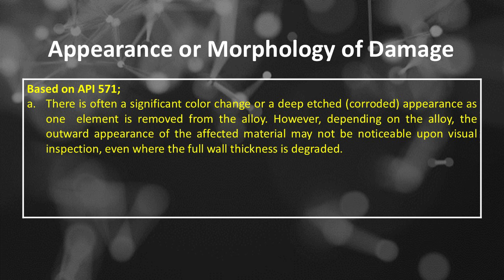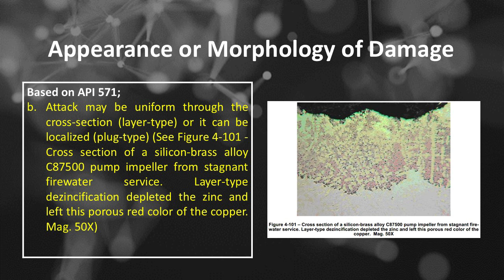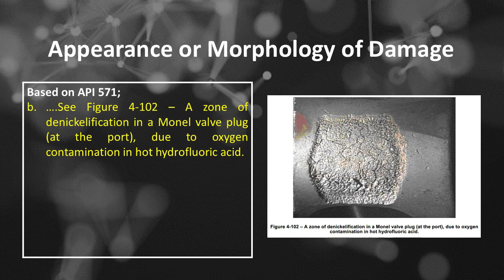B: attack may be uniform through the cross-section (layer type), or it can be localized (plug type). See Figure 4-101, cross-section of a silicon brass alloy C87500 pump impeller from stagnant firewater service. Layer type dezincification depleted the zinc and left this porous red color of the copper, magnification 50X. See Figure 4-102, a zone of denickelification in a Monel valve plug at the port, due to oxygen contamination in hot hydrofluoric acid.